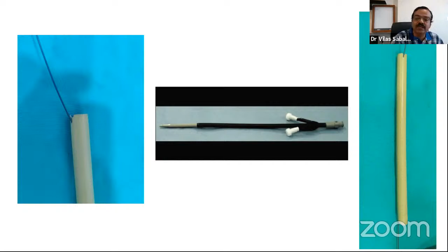This is a split peel-off sheath. Entry is easy. It has less blood loss. It keeps the intrarenal pressure low, allows visual clarity because of free inflow and outflow of the irrigation. Obviously, it reduces intrarenal pressure and the chances of extravasation. Stone fragments can be picked up easily when you are using larger sheaths, and with a smaller sheath, there is a whirlpool effect which has been popularized by Karl Storz, wherein the dust keeps on coming by the side.